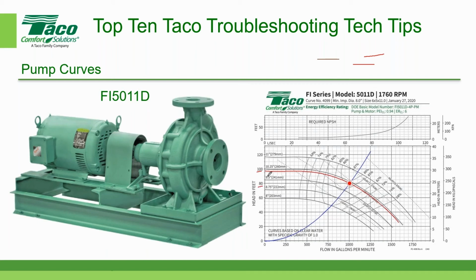So halfway between those two is 90. So this horizontal line is 90. And if I come over here, you can see that I'm going to try drawing a horizontal line right across here. And you can see that if it was 92 feet, it would be right on the pump curve. And so the actual flow, which they told me was 750 gallons per minute, is in fact a pressure differential of 92 feet. So what are we really talking about here?